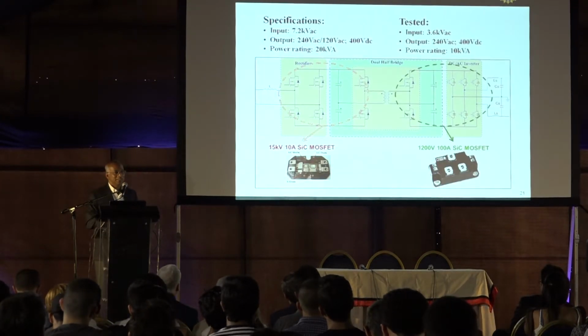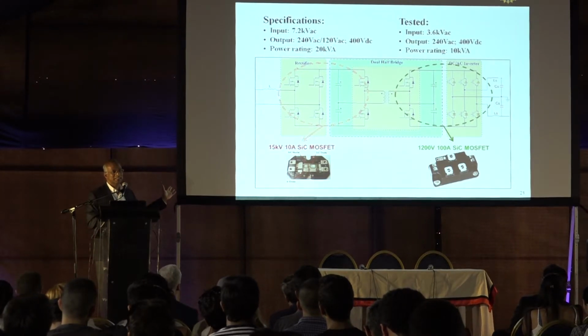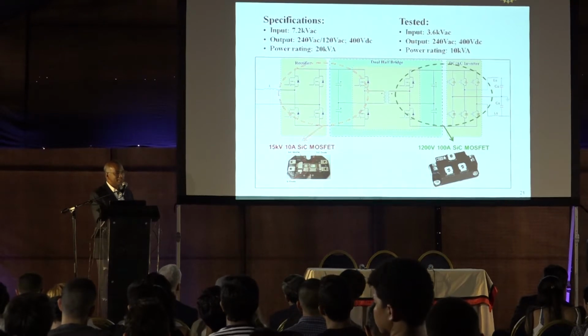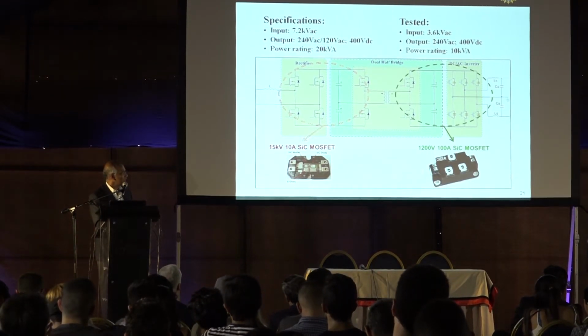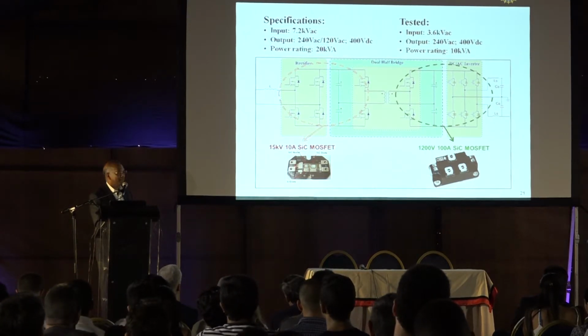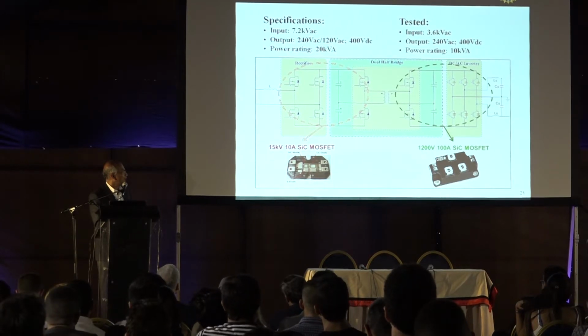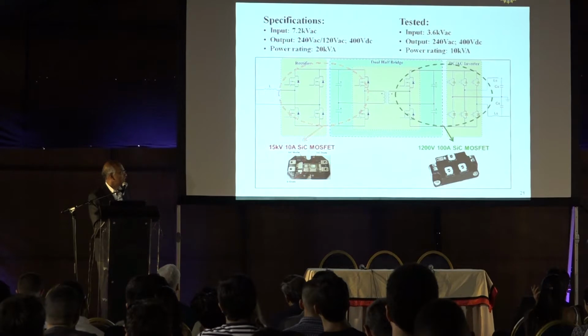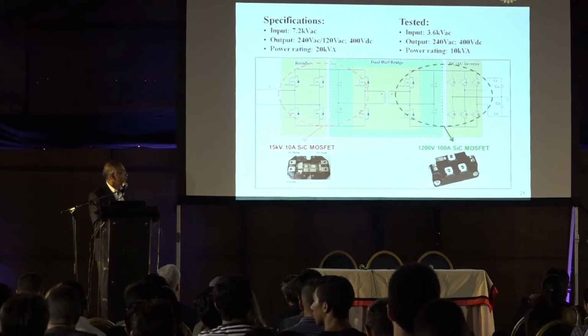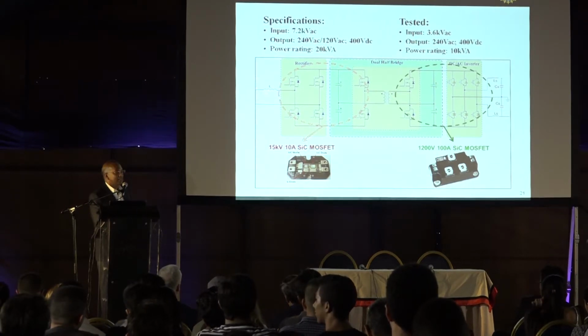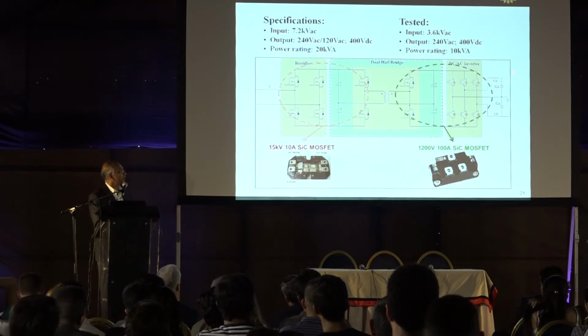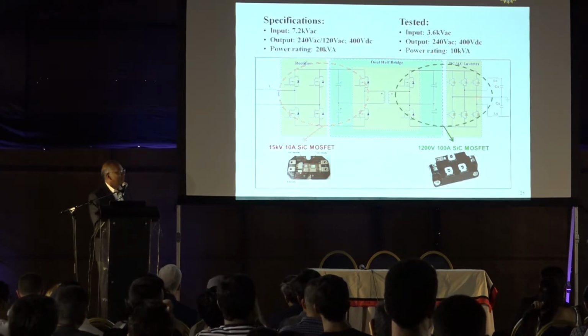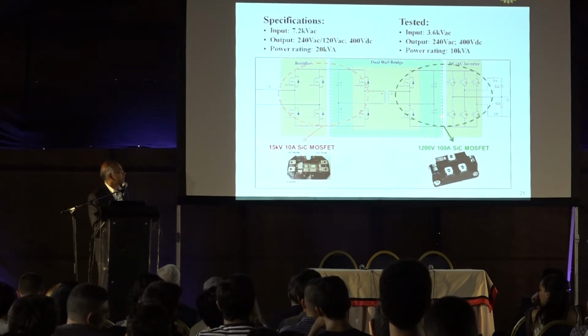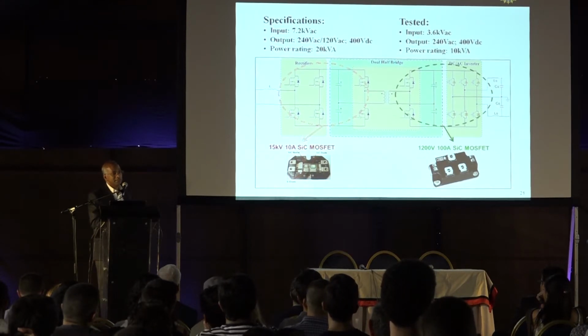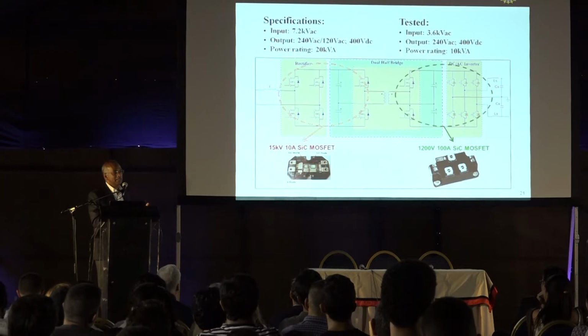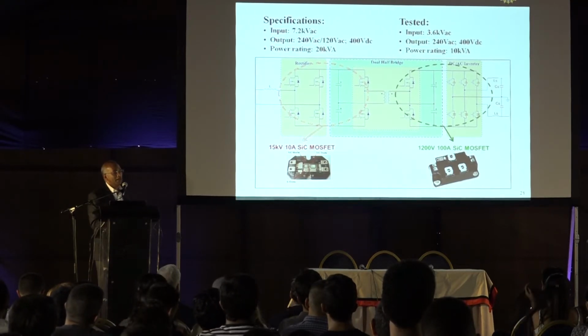So I'll not go into a lot of detail on these solid-state transformers, but this is just a circuit to show how it looks. It's an electrical circuit made of power semiconductor devices. Here it's showing a silicon carbide, wide bandgap semiconductor MOSFET at a higher voltage, one device itself going up to 15 kV. And this is on the low voltage side, 1200 volt, 100 amp. So this end gets connected to the medium voltage side, and this end is providing power to 240 volt or 120 volt split phase. And in between you have the DC. So DC can be supplied from here. Here there is a transformer, of course, like the regular transformer. But because it's operating at higher frequency and with these devices, it's much, much smaller and much more compact.